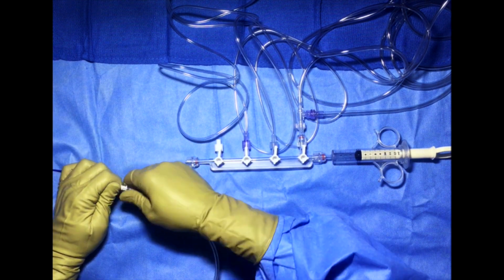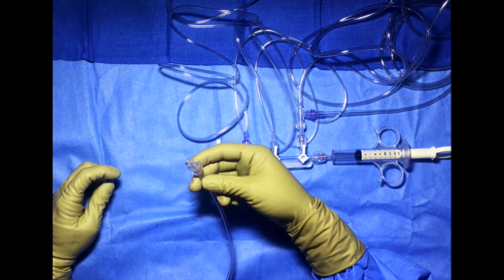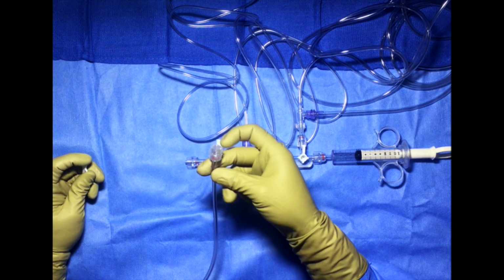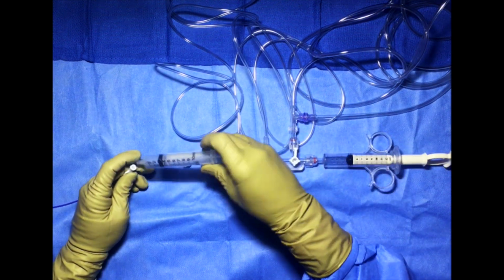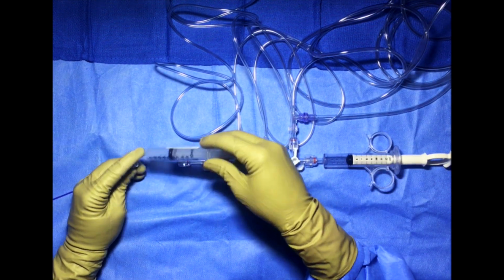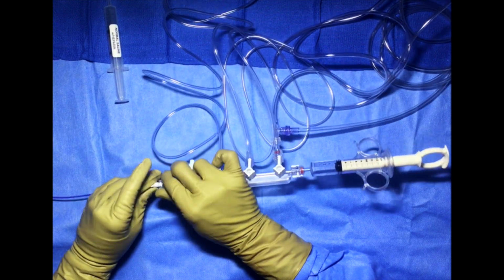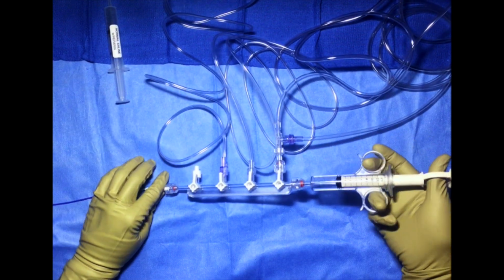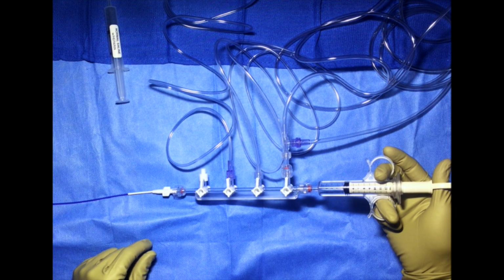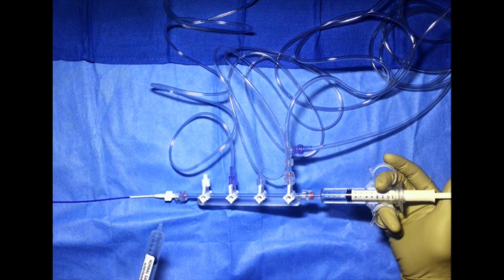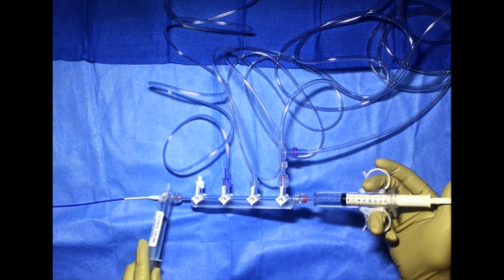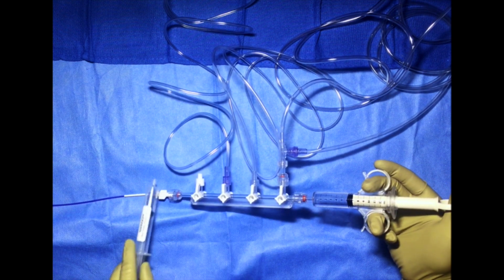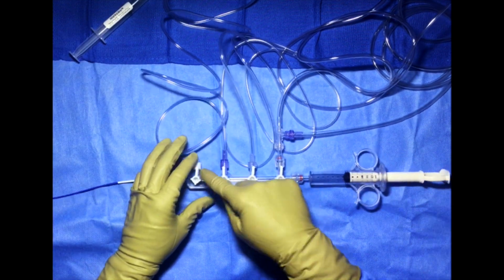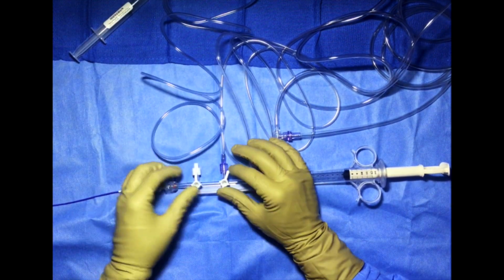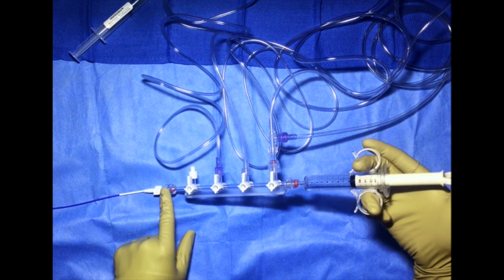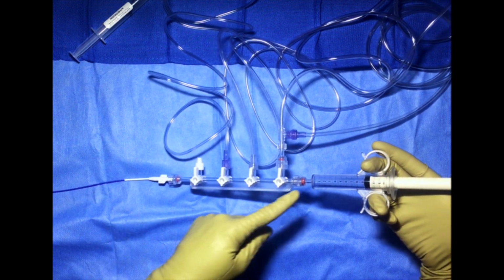Okay, so when we were done, we would unhook and cover it up to make sure no air can get in. We would take this off the table. Probably go ahead and do a little aspiration just in case, just to make sure. Connect here. What's the next thing I'm going to do? I'm thinking very specifically: I just connected here, so I'm going to go ahead and aspirate and tap all the way through here. Again, just to make sure nothing's here. Sometimes they'll go ahead and reflush everything, just to make sure, and re-zero even. Either way, we make sure there's no air here again. Connect, make sure there's nothing there, so you have to aspirate.